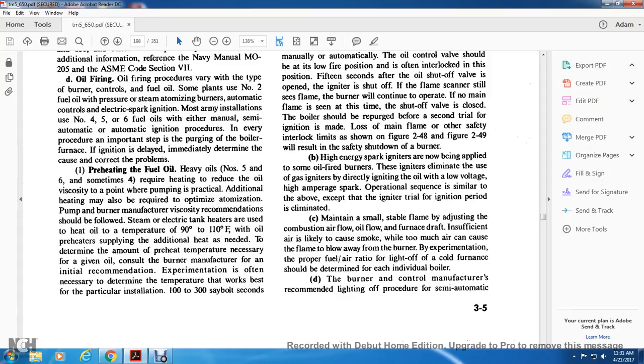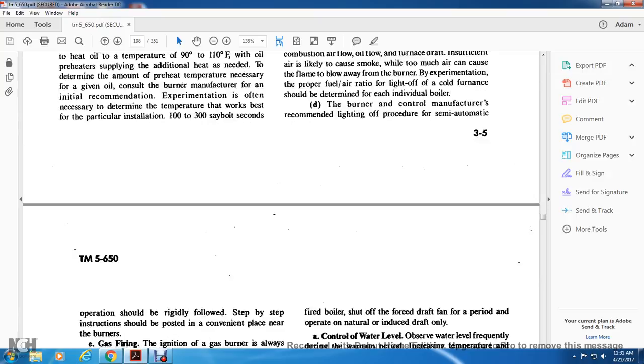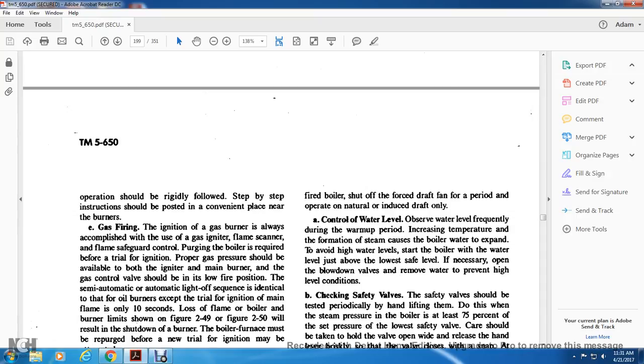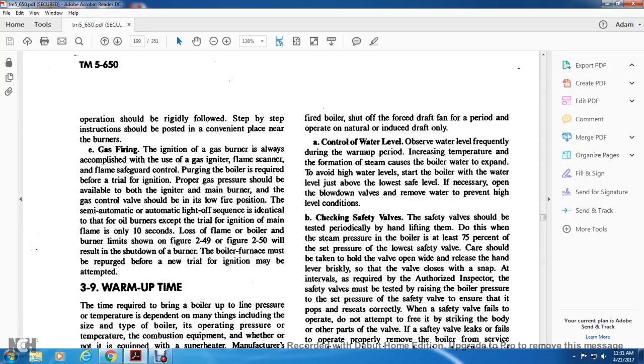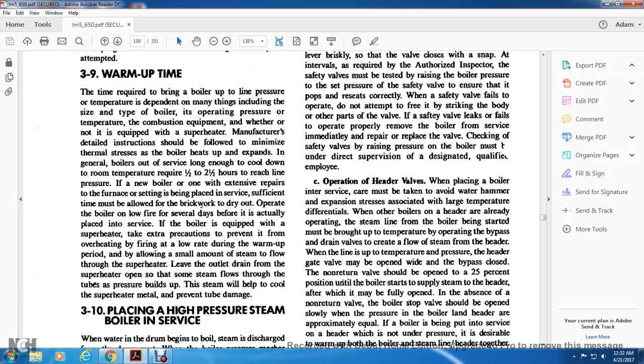Gas firing: initial gas burner ignition is always accomplished with a gas igniter, flame scanner, and flame safeguard control with purging of the boiler required. Proper gas pressure should be available for the igniter and main burner, and gas control valves should be in low fire position. The semi-automatic light-off sequence is identical to oil burners except the trial for ignition of main flame is only 10 seconds. Loss of flame and boiler burner limits shown in figures will result in shutdown of the burner. The boiler furnace must be repurged before a new trial of ignition may be attempted.